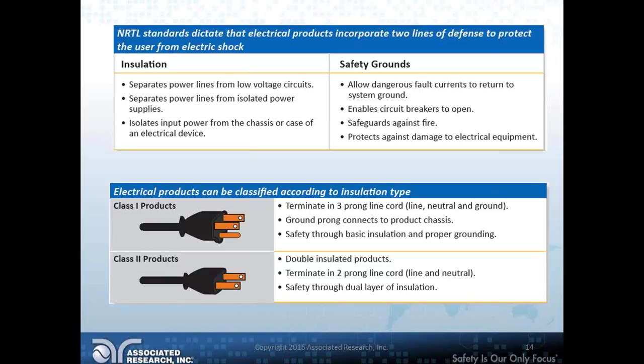Class 1 products generally will terminate in a 3-prong cord - something as simple as everything you use at home. For example, maybe your vacuum cleaner has 3 prongs. Most computers don't, they're usually dealing with a 2-prong. But that third prong - you have your 2 blades, as you can see in that picture, and then that round prong at the bottom, essentially the mouth of the smiley face, as I like to say when you're looking at an outlet. That's your ground prong, and that basically gives you safety through basic insulation and proper grounding. So you have your insulation and your grounding as your two means of protection.